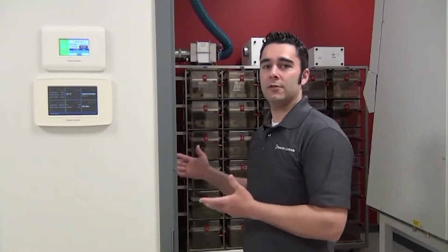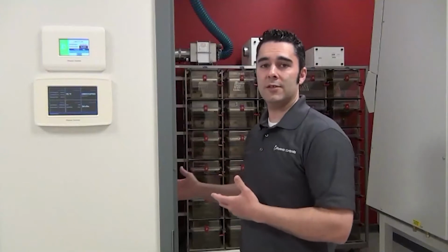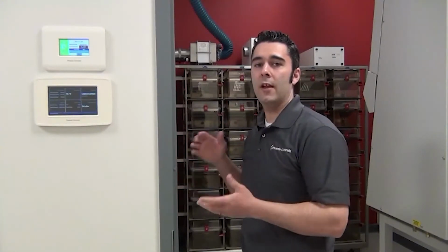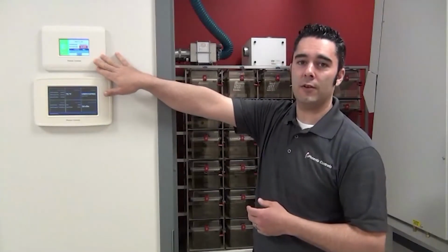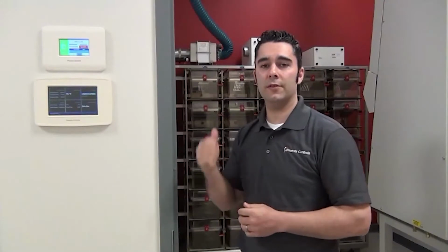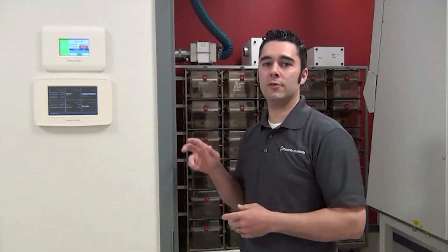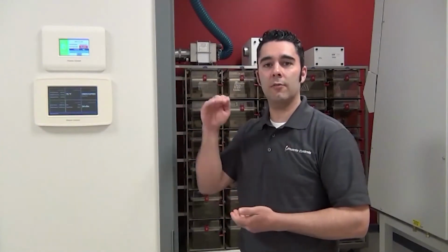But in this type of an environment, because you're using biological chemicals potentially, or you're going to be doing testing on animals that may have no immune systems, you need to guarantee that those animals are safe. So instead of having a fixed volumetric offset, we're actually going to monitor the differential pressure across the door and vary the volumetric offset to maintain a differential pressure set point. The application that we use for that is called Progressive Offset Control, or POC. And how that effectively works, the pressure is being monitored from the transducer that's in this model here. It is actually hardwired back to the system on the Solaris 2 valve, and it's going to be looking at the differential pressure across the door and actually running a PID loop to increment the volumetric offset and maintain that differential pressure. So for example, in this particular room, I might have a negative differential pressure set point of 0.02 inches water column, and I need to maintain that at all times.